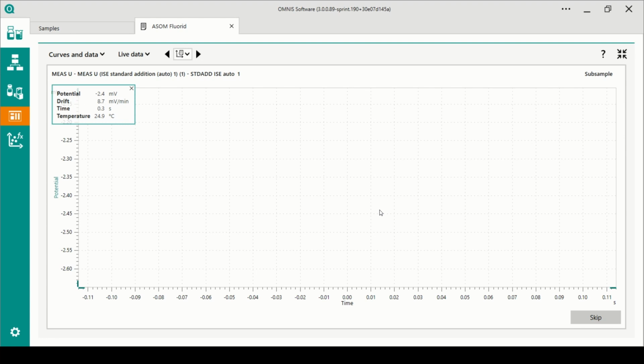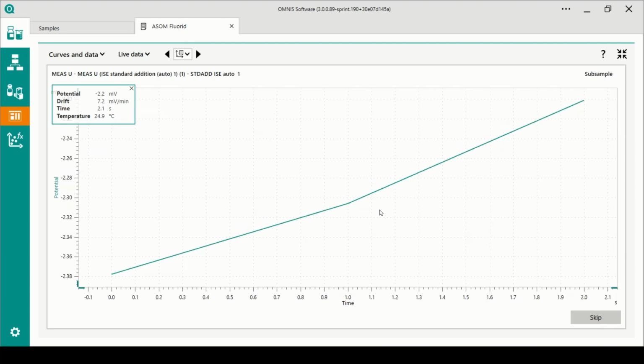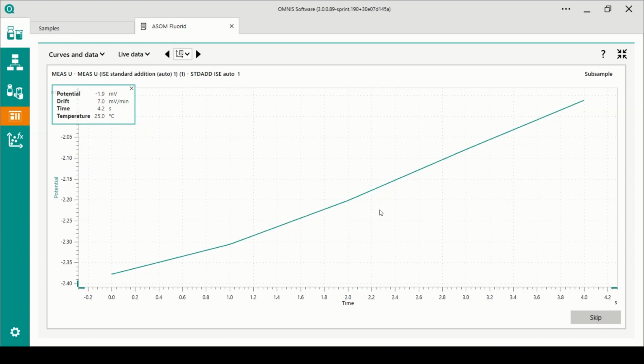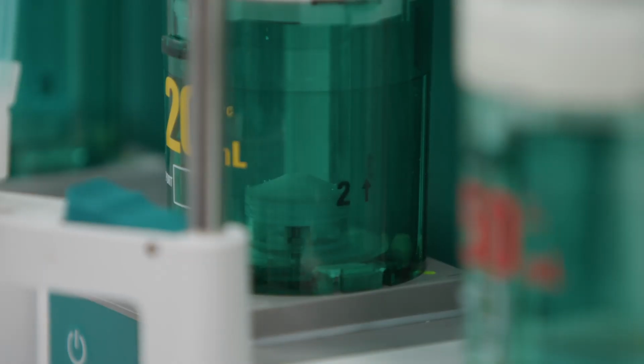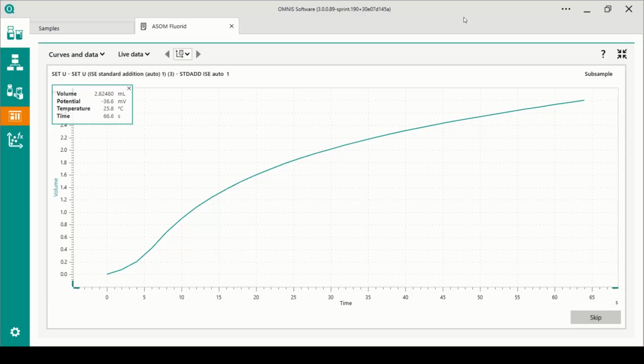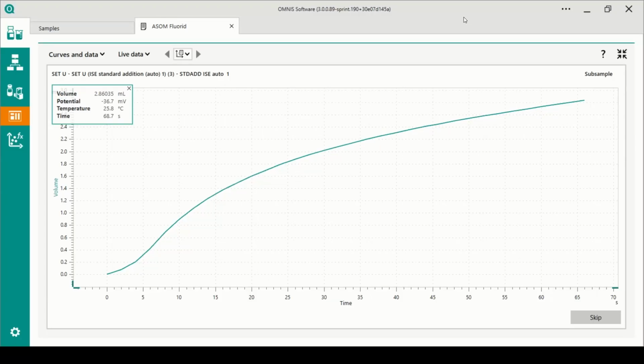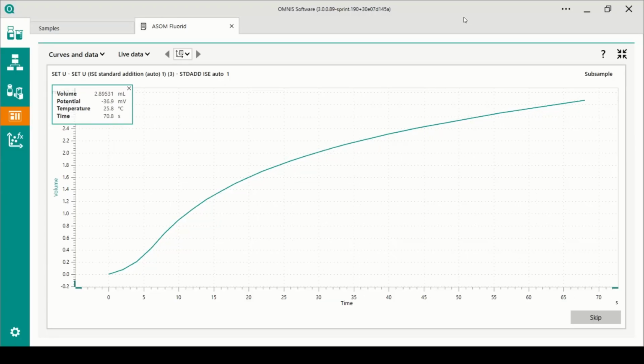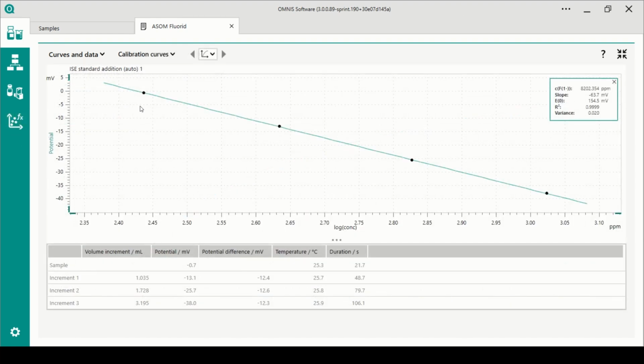First, the start potential is measured. Afterwards, increments of fluoride standard are added to the sample. We recommend to add at least 4 increments. You can decide to add either constant volume increments or add standard until a predefined potential difference is reached. Once the standard addition is finished, the result is calculated and displayed immediately in the software.